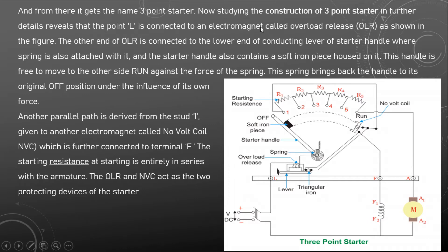Studying the construction in further detail reveals that point L is connected to an electromagnet called the overload release (OLR). The other end of the OLR is connected to the lower end of the conducting lever of the starter handle. A spring is also attached to this conducting lever.